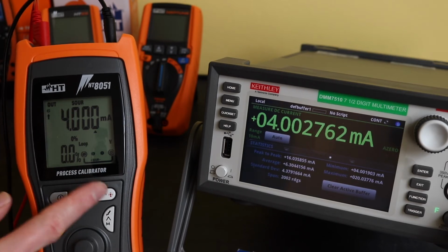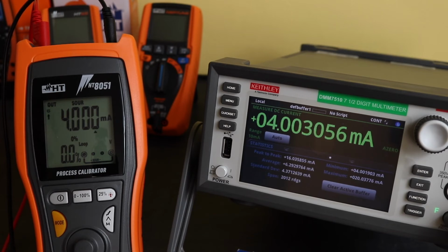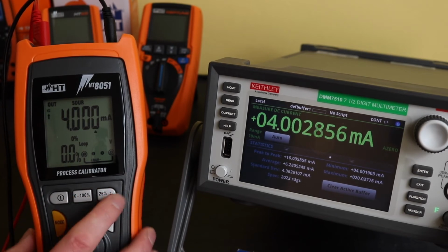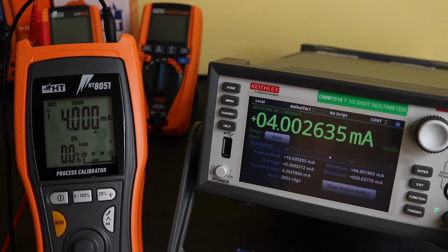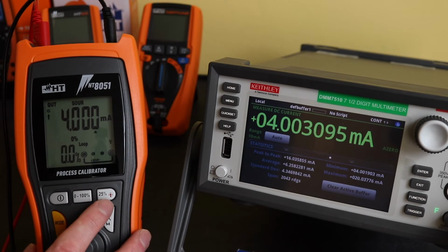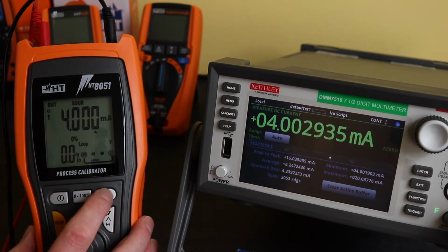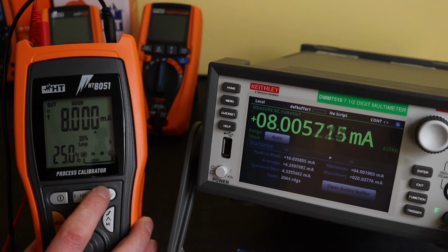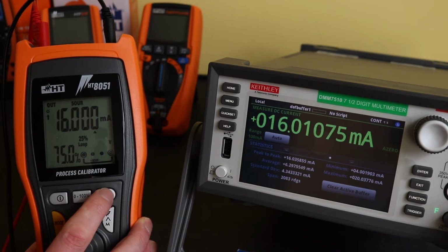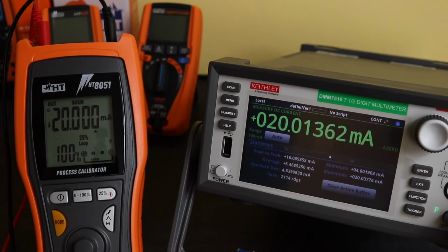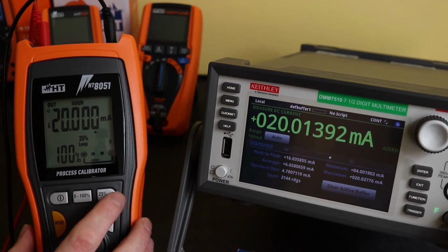What I'll do now is use the 25% button just to step this through the range of the output for some accuracy checks at the 4 points here. So we're on 4 milliamps, and you can see we've got 4.0026-ish, 32, yeah, oscillating a little bit on those last 4 digits. Let's go to 8 milliamps, that's that one there, 12 milliamps, 16 milliamps, 16.01, starting to get a little bit out now, 20 milliamps, 20.0137-ish. 381 again, those last 2 digits oscillating around a little bit. Okay, so that's the accuracy on that one done.